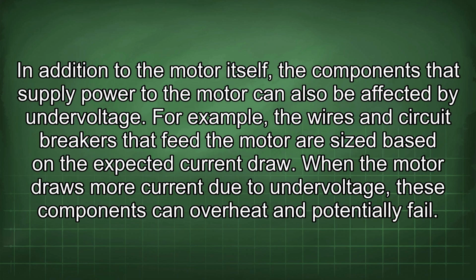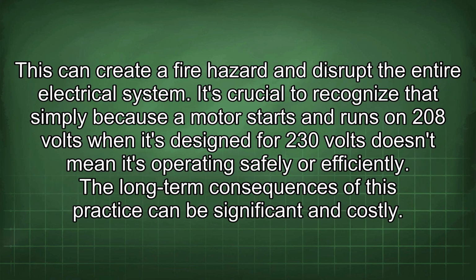In addition to the motor itself, the components that supply power to the motor can also be affected by undervoltage. For example, the wires and circuit breakers that feed the motor are sized based on the expected current draw. When the motor draws more current due to undervoltage, these components can overheat and potentially fail. This can create a fire hazard and disrupt the entire electrical system.